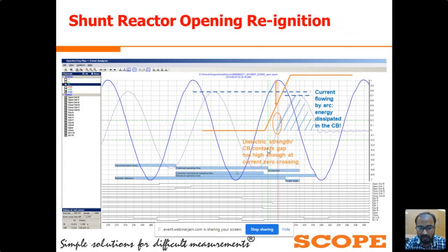At this moment, the dielectric strength between the CB contacts is less than the system voltage. So due to that, the current continuously flows between the CB contacts. At this moment, the current goes to natural zero, but still the dielectric strength between the CB contacts is less than the system voltage. So due to that, there is a reignition we have observed here.